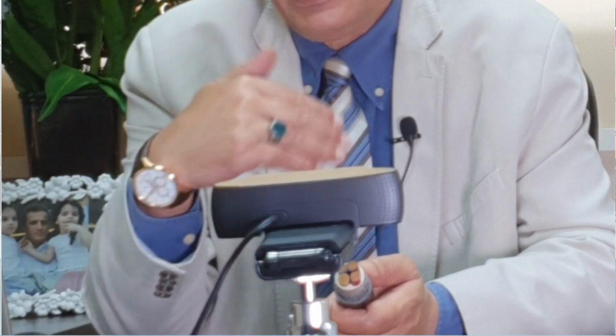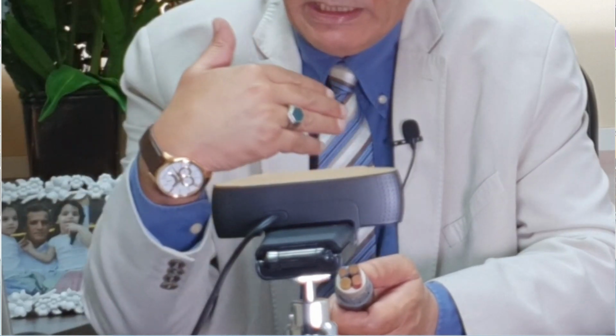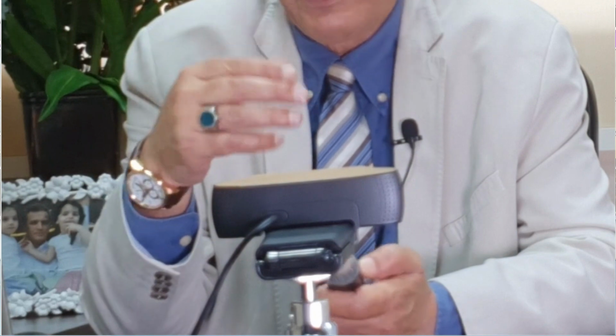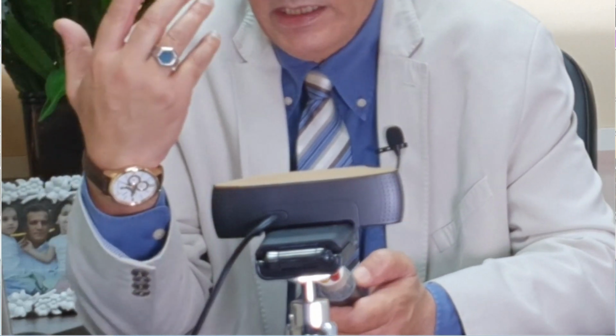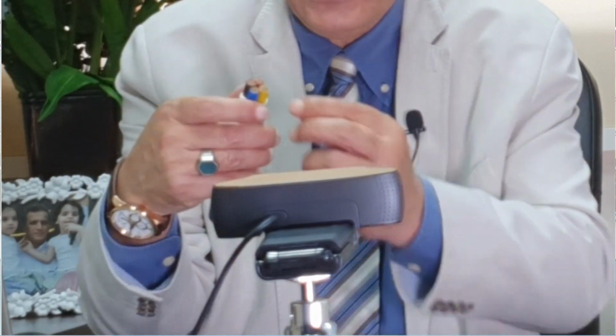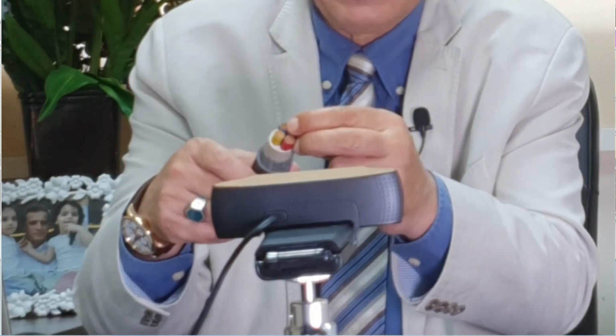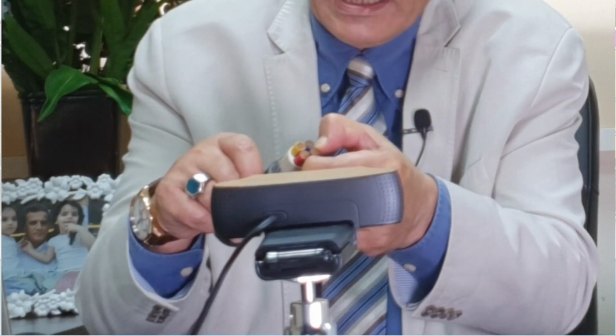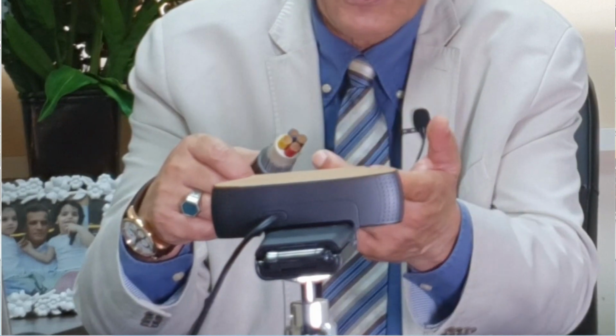In a three phase system, suppose I am laying a cable to feed one factory, and I want the voltage drop for this cable. This cable is three phase. For my calculation, I take the length of the cable for the resistance or inductance. Why? Because each phase has a current, but the neutral one, if it's a balanced system—which is assumed—will be zero. So I have only one conductor from the source, the sending end, to the receiving end in three phase.